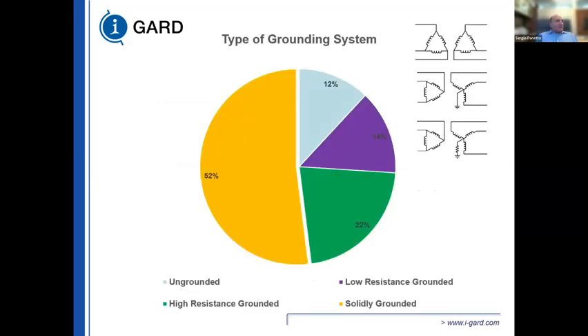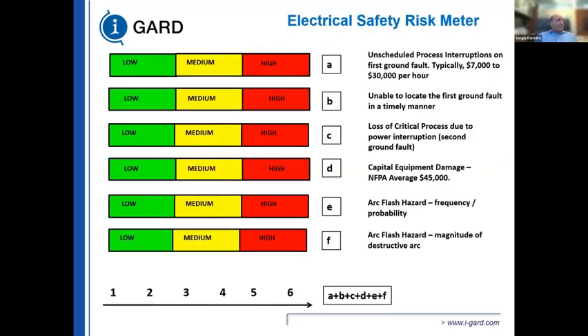The types of grounding used on systems in the world today are ungrounded systems, low resistance grounded systems, solidly grounded systems, and high resistance grounded systems. You can see the change in usage of each of those. We've gone to our marketplace and come up with an electrical risk meter with questions to our audience. Unscheduled process interruptions on the first fault, typically 7,000 to 30,000 is A. The inability to locate the first ground fault in a timely manner. Loss of critical process due to power interruption, capital equipment damage, on average greater than $45,000, and arc flash hazard magnitude. When you add up all these numbers, you come up with a risk assessment.